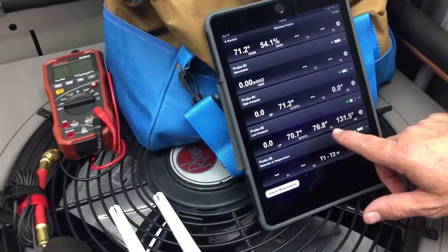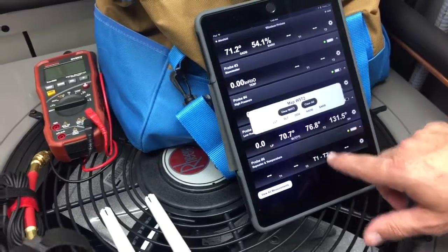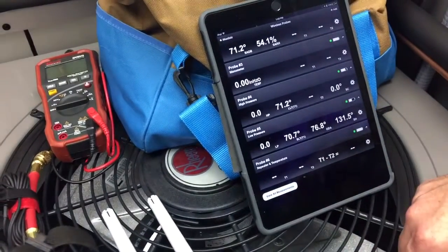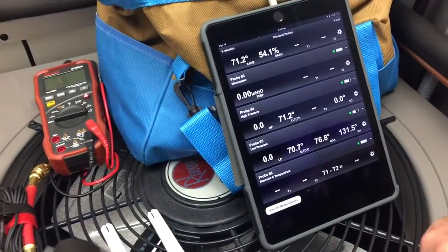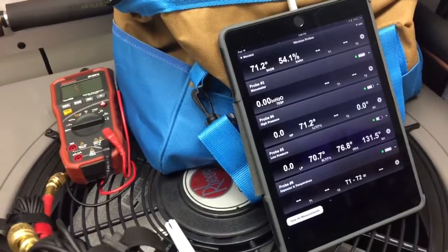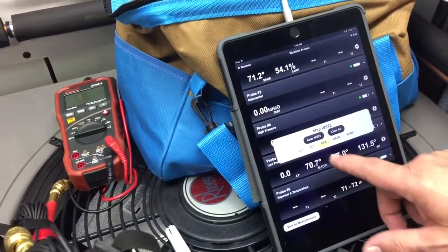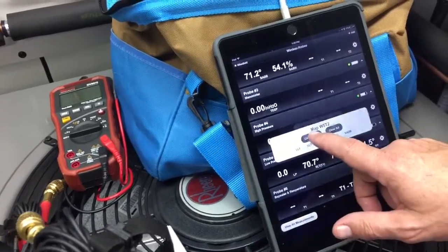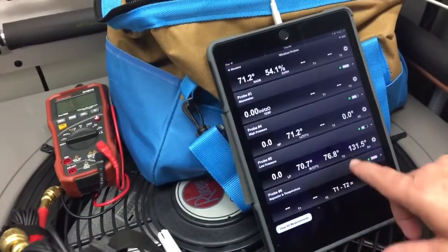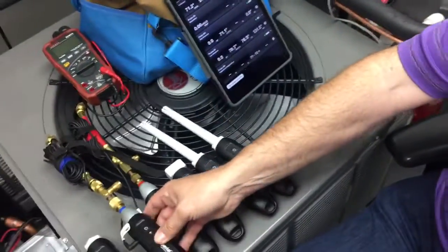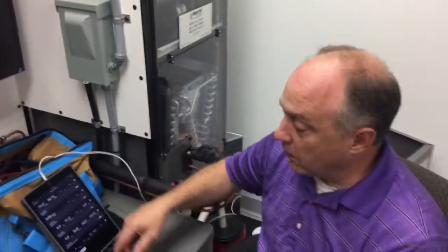You'll see that the T2 on the low pressure probe is going to report 76.3 degrees. I'll just tap on that, tap that to outdoor air, and now that's mapped to the outdoor air temperature. So it's just as simple as that. Now I want to take that back off there, I can just clear that mapping. So I'll clear W5T2, hit clear, and now that's back to just a standard T2 terminal. So it's very easy to map the probes and do what we want to do.